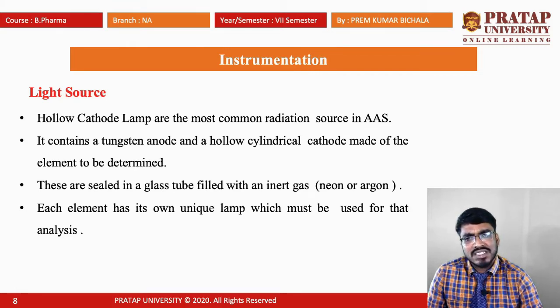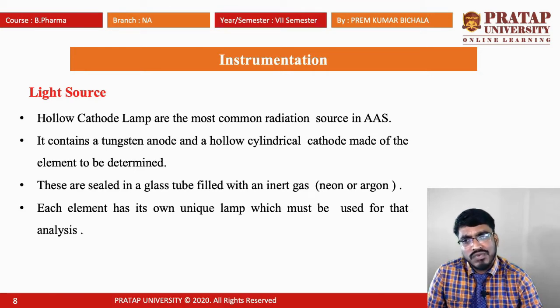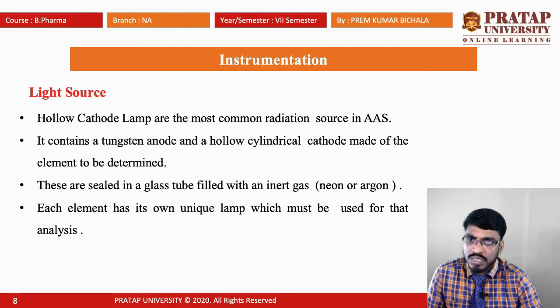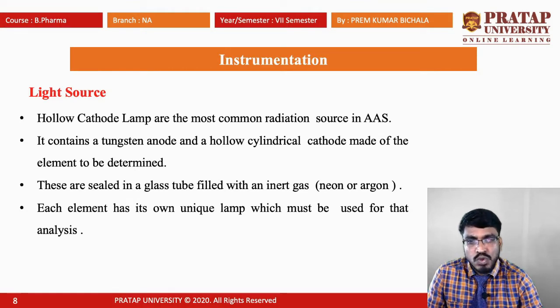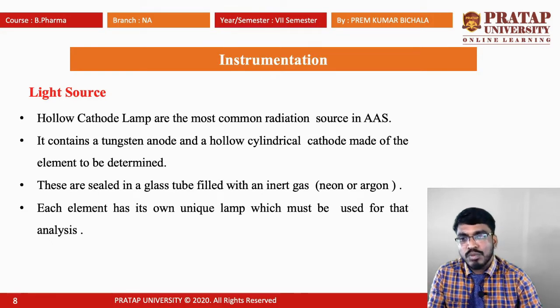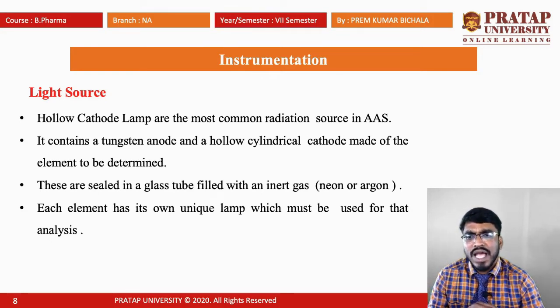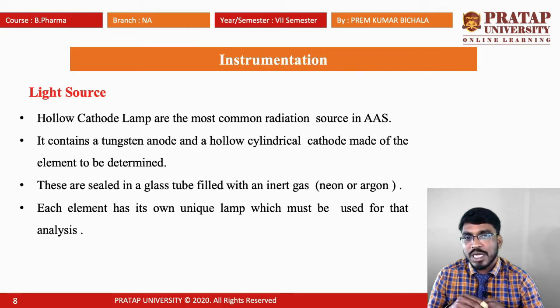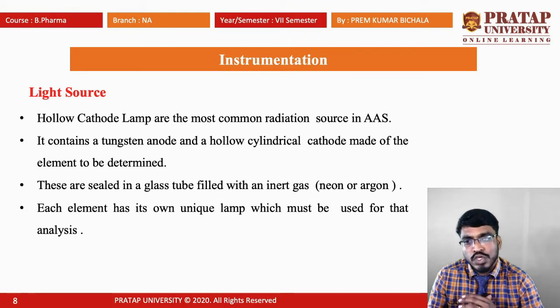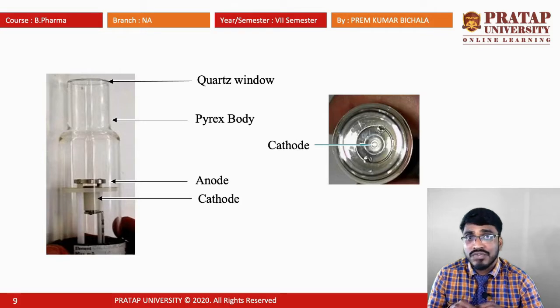The hollow cathode lamp contains a tungsten anode and a hollow cylindrical cathode made up of the element to be determined. The construction of the light source depends on the metal which we are going to determine. These are sealed in a glass tube filled with an inert gas — mostly neon or argon is preferable. Each element has its own unique lamp which must be used for that analysis. The cathode should be made up of the element we are going to determine. This is the construction of the hollow cathode lamp.